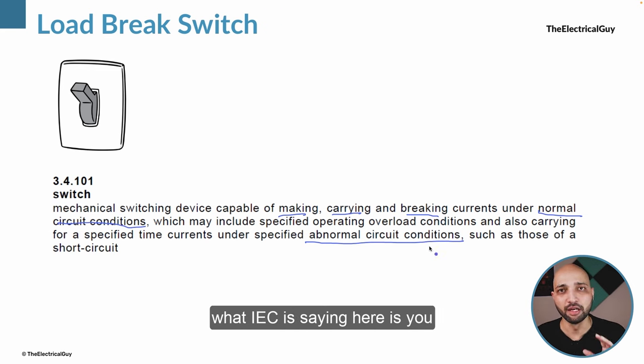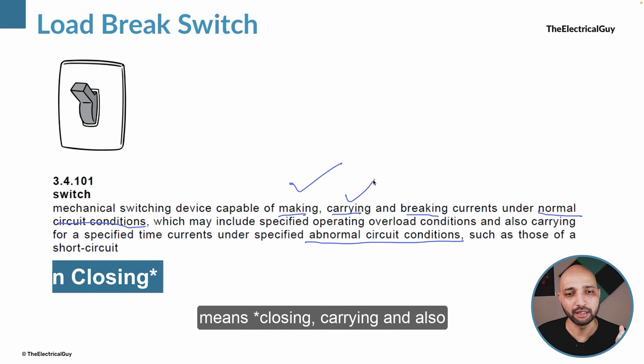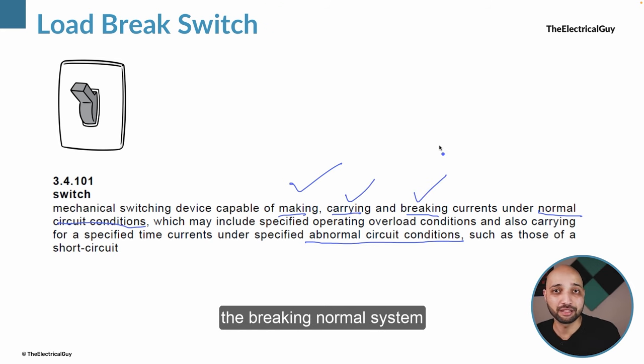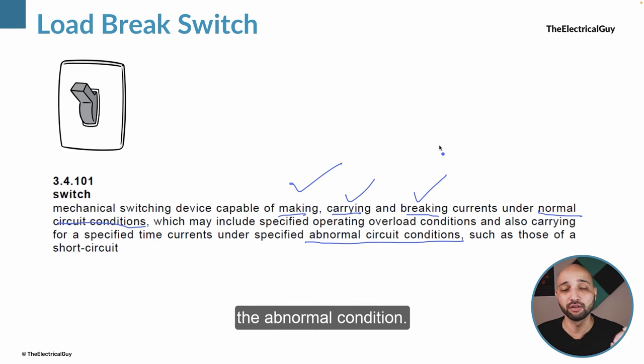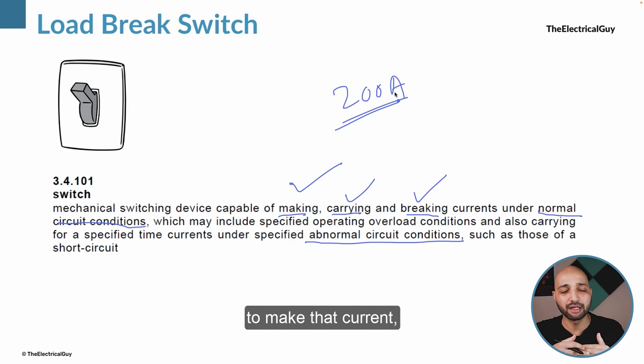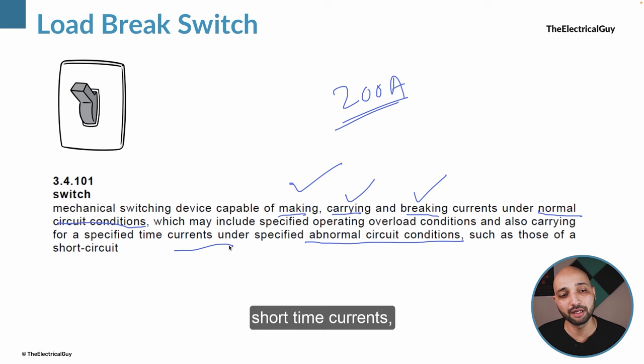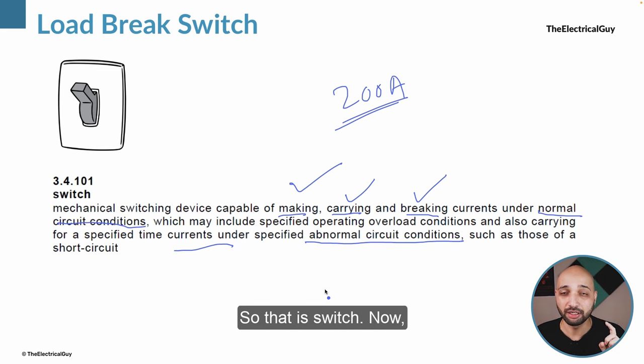IEC is saying that you can call something a switch when it has the capability of making, carrying, and breaking normal system current — not abnormal current, normal current. So if your system's normal current is 200 amperes and your switch is able to make, break, and carry that current, it can be called a switch. Additionally, the switch will have capability to carry short-time currents which can occur because of faults for specified time limits.